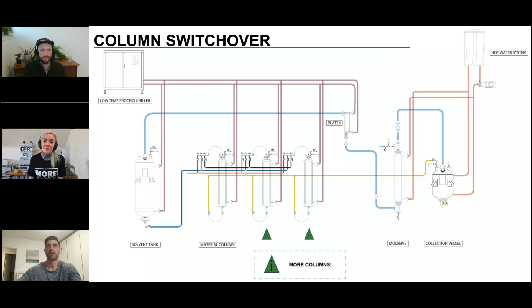The next kind of bottleneck we see a lot of is active recovery. Active recovery is when you use a compression pump to recover your solvent, and it's limited by a number of things. One is that you have a fixed displacement inside these pumps, so you can only draw in as much gas as it can hold. The only way to increase your process speed is to buy more of these pumps.